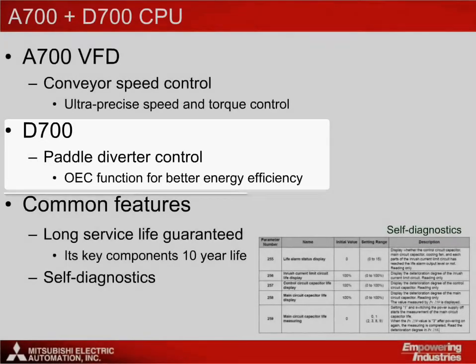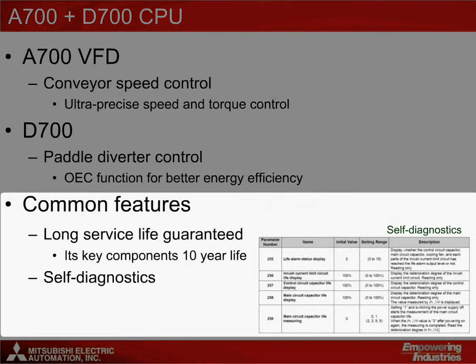An internal measuring program monitors the aging of the capacitors, and an operating hours counter enables the operator to plan the best time for servicing. Protection overload functions like the phase failure monitoring system for both input and output circuits ensure trouble-free operation.